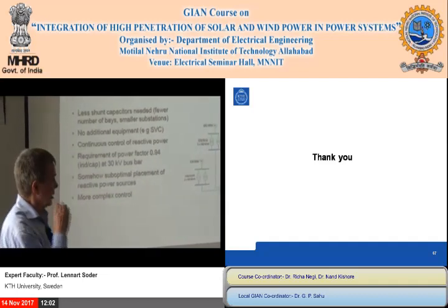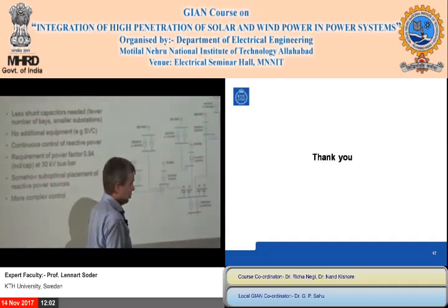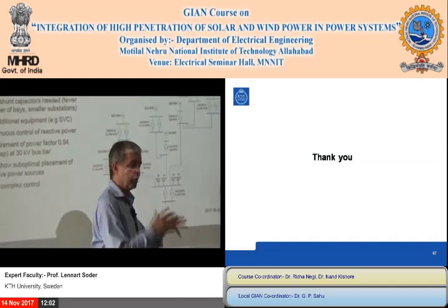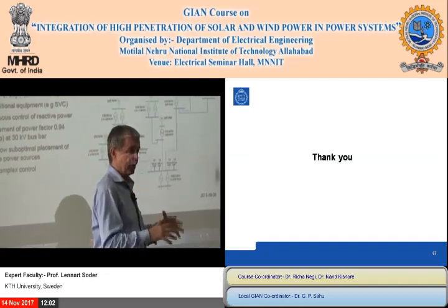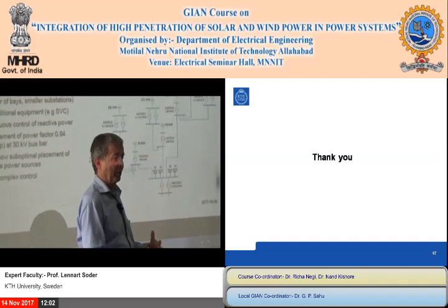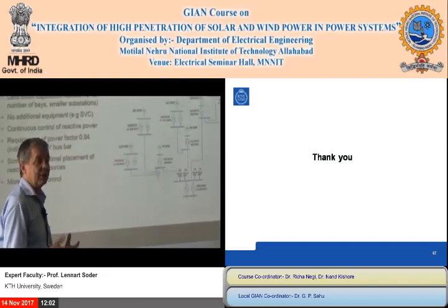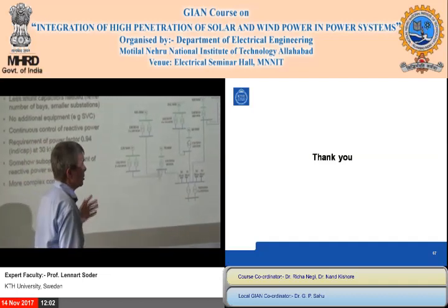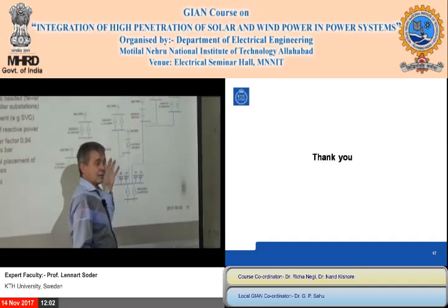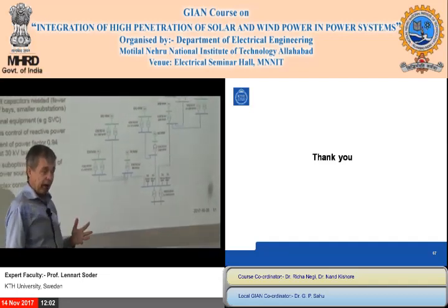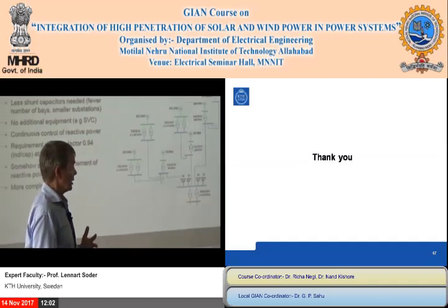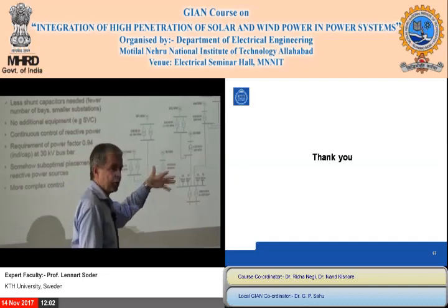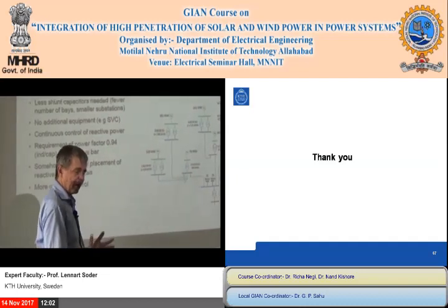And the whole idea is what I talked about earlier several times. I'm not talking about a little wind power now, I'm talking about high penetration, situations when the whole country is supplied only with solar and wind power. Then of course you need transmission, and you need to keep the voltage in the transmission system. One alternative is to do that with the available controllable capacities in the wind and solar power. In the German grid, we are currently checking if the solar power could also control the reactive support at the feeding point to the transmission grid. They have other projects in that.